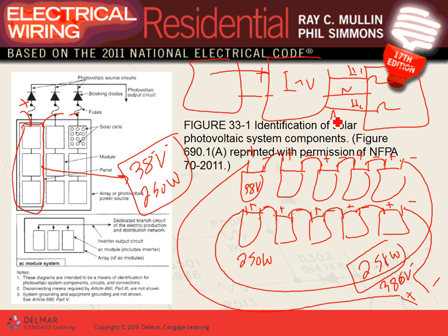So now you got your AC here, you got your DC here. This is a DC to AC converter. That inverter is an electronic piece of equipment that chops the electricity and converts it from DC into AC. It interrupts the DC electronically and creates an AC system. And the system that we use in dwellings is a 240/120 volt system. That's exactly a typical installation: 10 panels, 250 watt, 380 volt, one of the typical installations that you can do in a house.